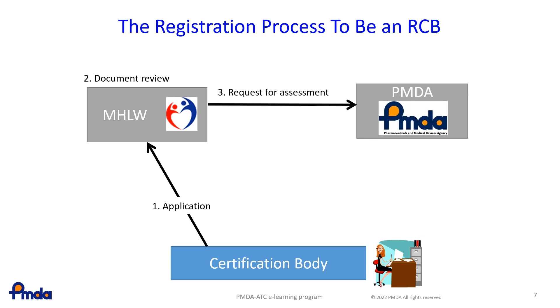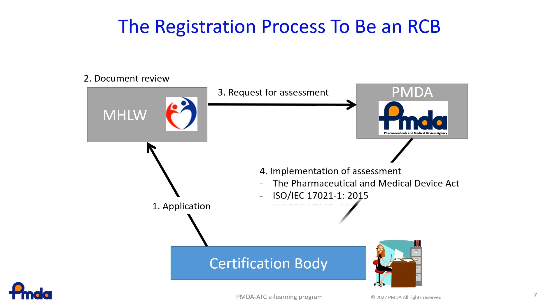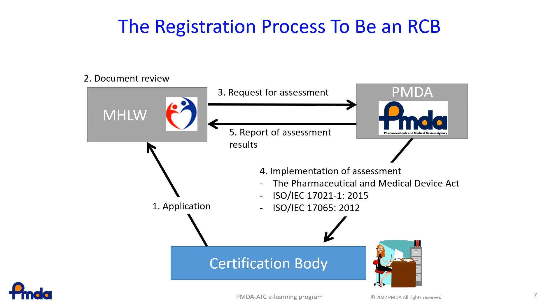After the document review, MHLW requests PMDA to assess the certification body. The PMDA then conducts an on-site assessment of the certification body to confirm conformity to the requirements stipulated in the Pharmaceutical and Medical Device Act and the relevant standards, which include ISO/IEC 17021-1 and ISO/IEC 17065.